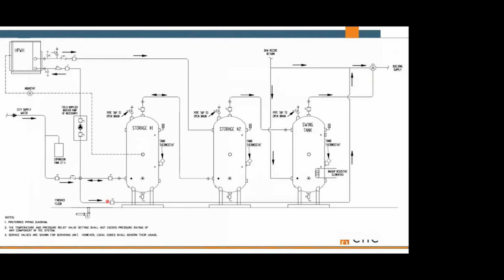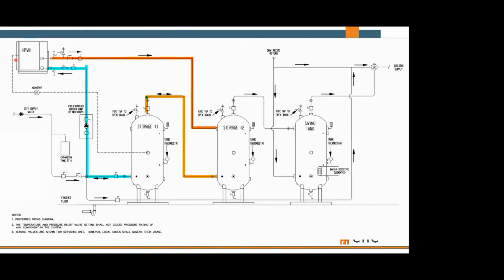Let's talk about how these might work in the field. Because if you see a piping schematic like this, you're like, oh, this doesn't make sense. Well, there's too much going on here. We've got multiple tanks, one heat pump water heater, city coming in. We've got a recirc. Okay, this is a head scratcher. So when you're designing a heat pump water heater, one of the things you have to figure out is how often is it going to run, or what's the off peak?